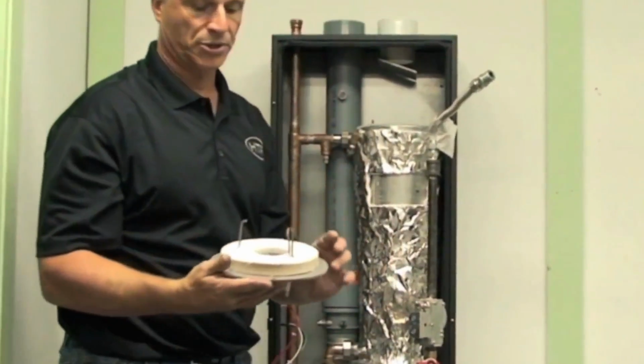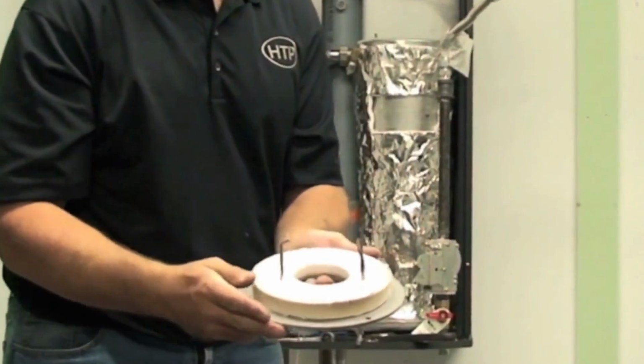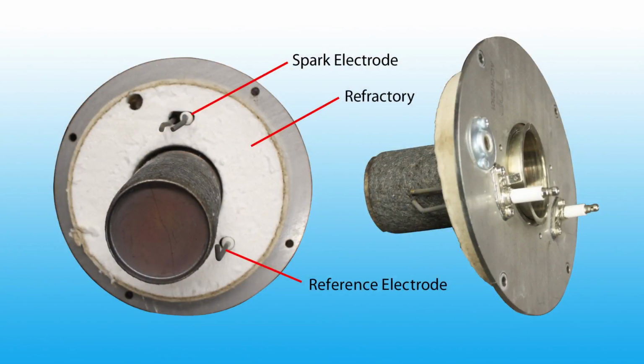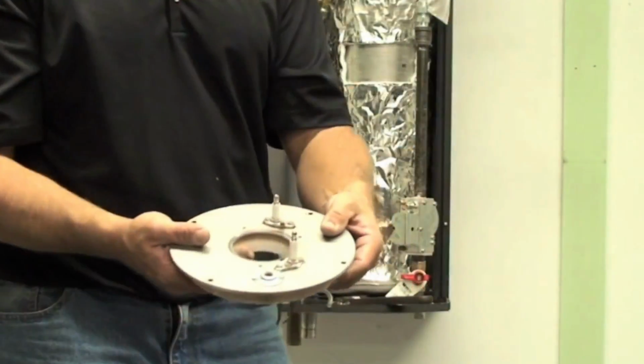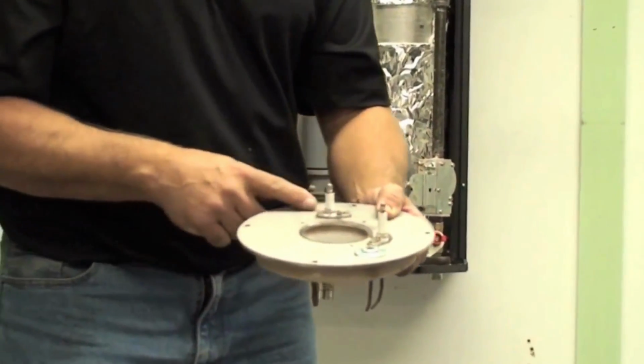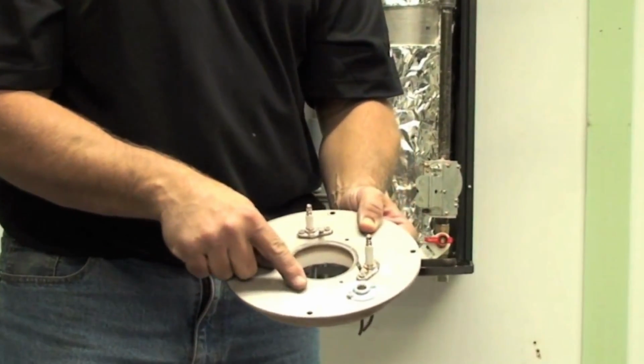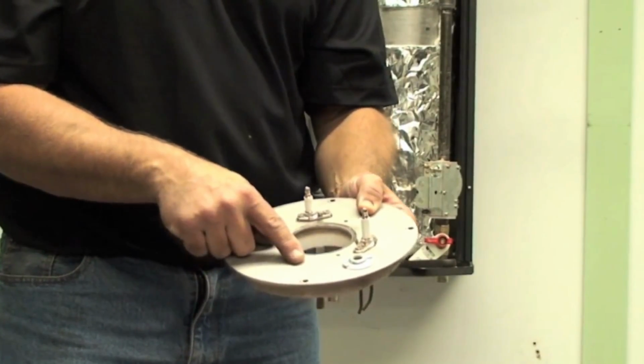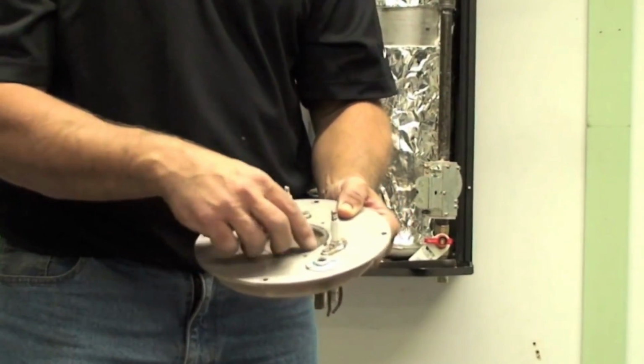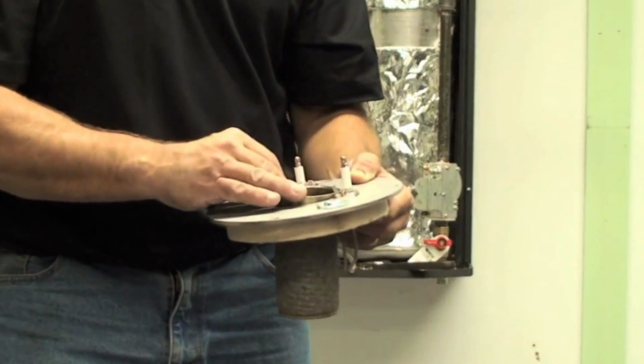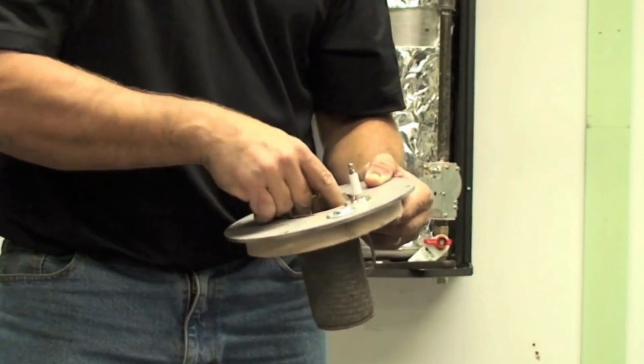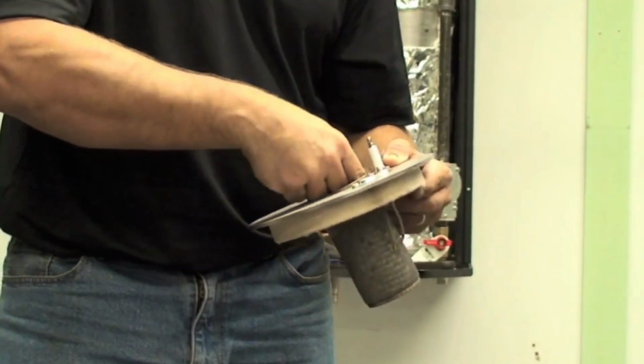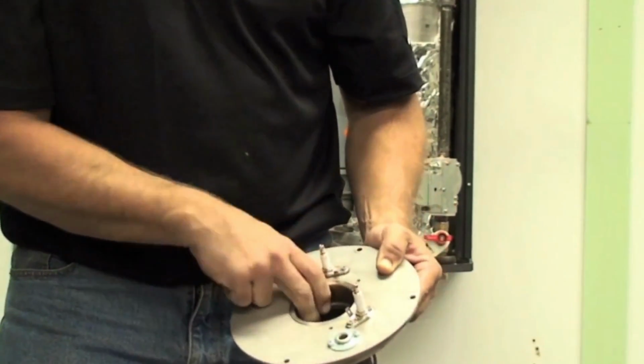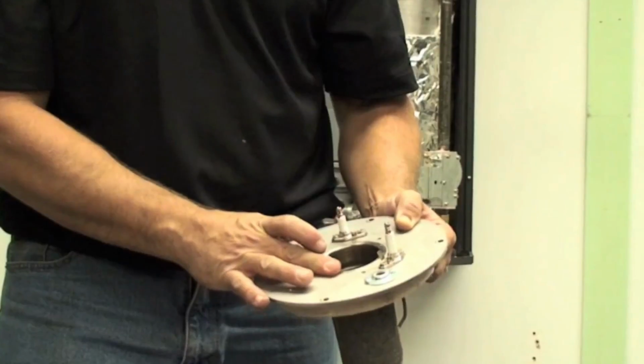The plate comes out with the combustion gasket. This is a refractory. Okay, so you can see your spark electrode, your reference electrode. This is your refractory. You can kind of see how the burner door, it's all laser cut. You can see that it's even indicated what the top of the door is. And again, we have our little notch here, so when you lock in your burner, this is a little bit easier to see. You can see you can only do it in one position. Okay, and that's a proper seat.